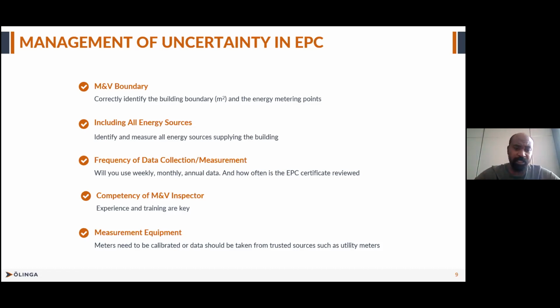One project I looked at was for a massive utility owner. The senior manager I spoke to mentioned that multiple buildings can be fed from the same substation, and sometimes multiple buildings are metered from the same meter. So when going to site, it's necessary to delineate which meter is metering what, and if different buildings share a meter, you'll have to segregate or disaggregate the energy consumption, which might mean installing a separate meter.